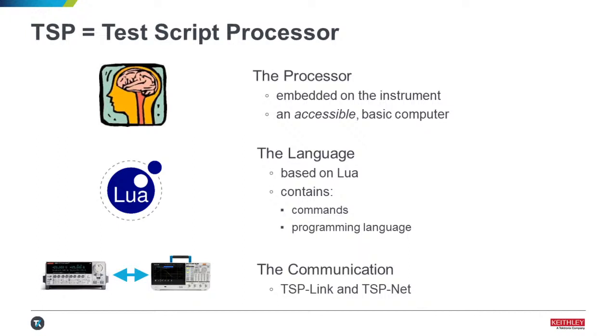The processor aspect of TSP is that all TSP-enabled instruments, like all the 2600 SMUs that we're talking about today, have an embedded processor on the instrument itself. So that means that the instrument can execute TSP code without being connected to a computer.